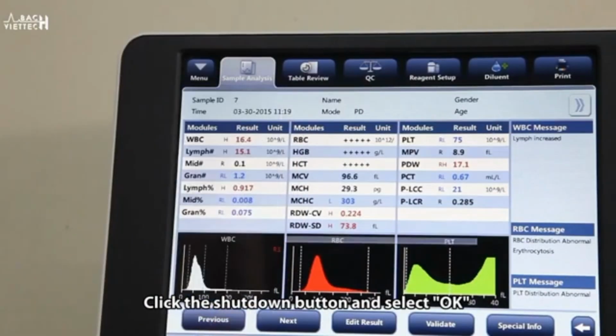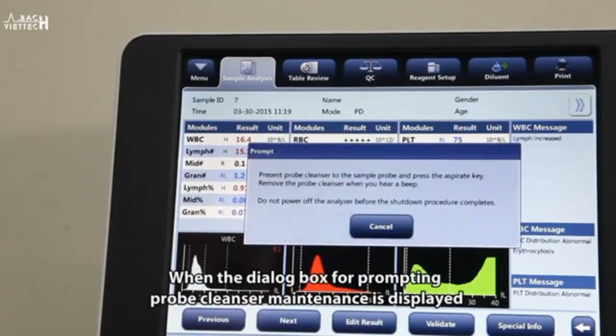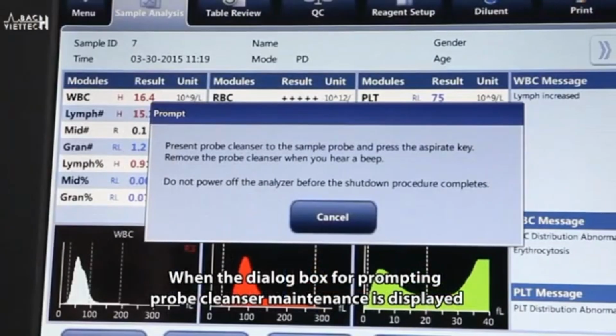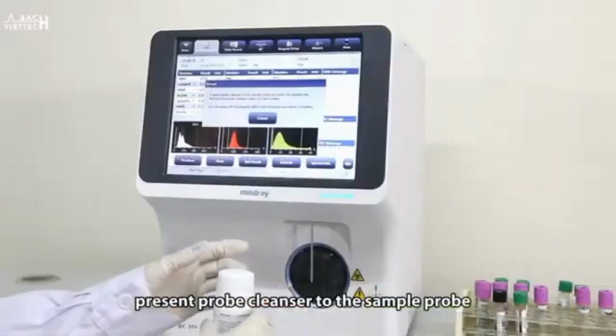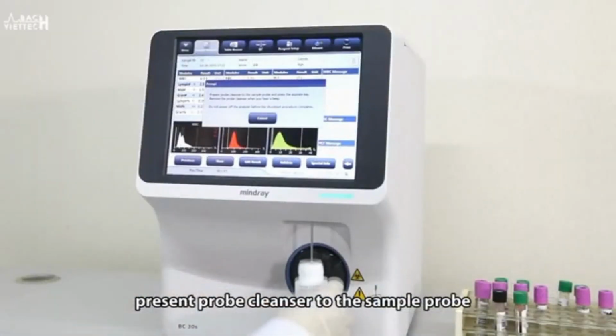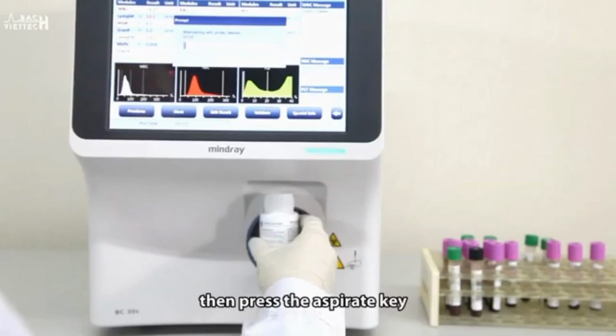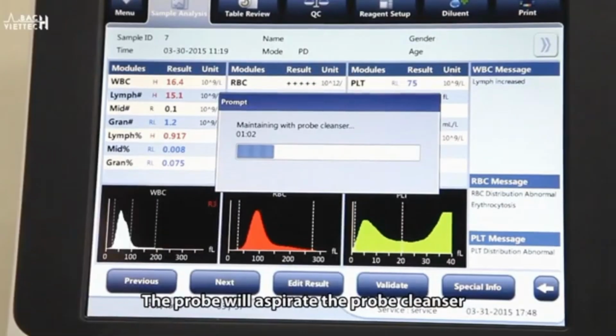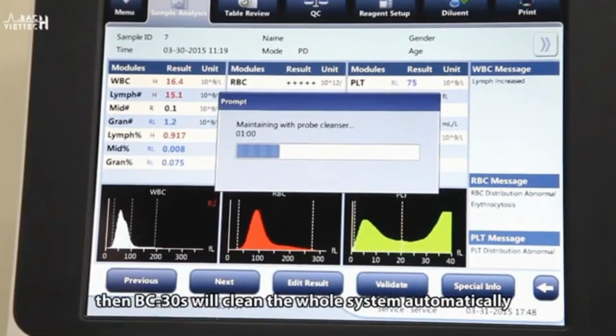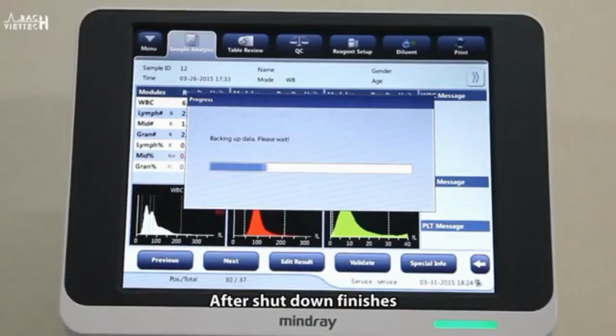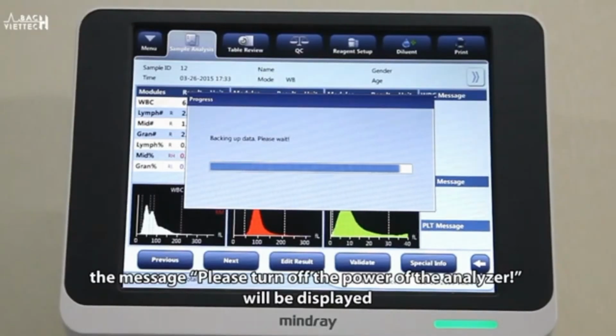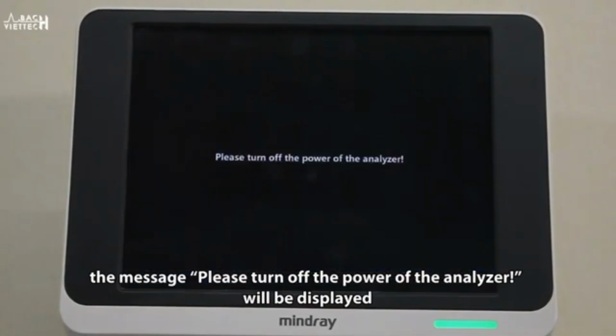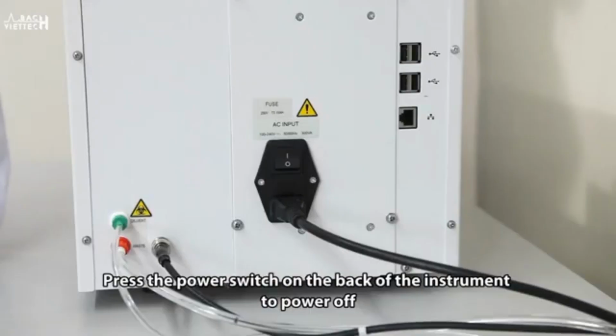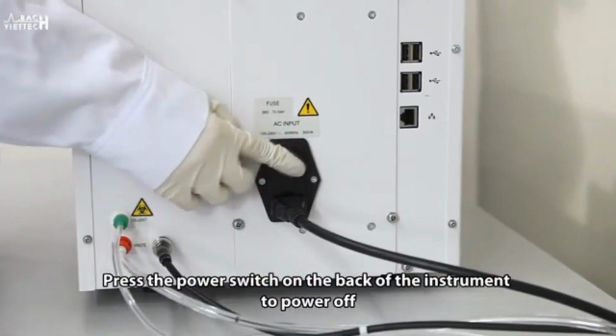Click the Shutdown button and select OK. When the dialog box for prompting probe cleanser maintenance is displayed, present probe cleanser to the sample probe. Then press the aspirate key. The probe will aspirate the probe cleanser, then BC30S will clean the whole system automatically. After shutdown finishes, the message, "Please turn off the power of the analyzer," will be displayed. Press the power switch on the back of the instrument to power off.